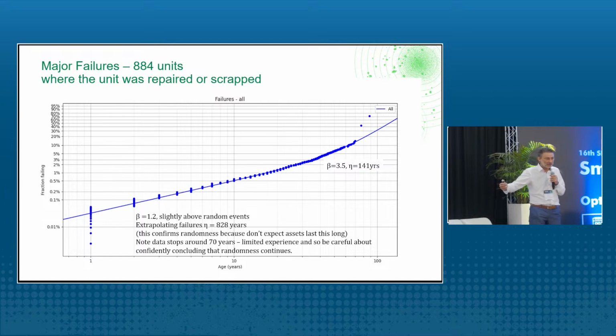So 140 years. I said in the beginning 30 years is the expected lifetime of the transformer. Here, the statistic shows it's 140 years. So the North Americans did it correctly. 140 years, no problem for a transformer. Let's keep it in operation. So transformer failures are due to random events. And this means time-based maintenance, the idea to exchange a transformer after 30 or 50 years, is nonsense for transformers. From economic reasons, this is not good, because it can survive much longer.